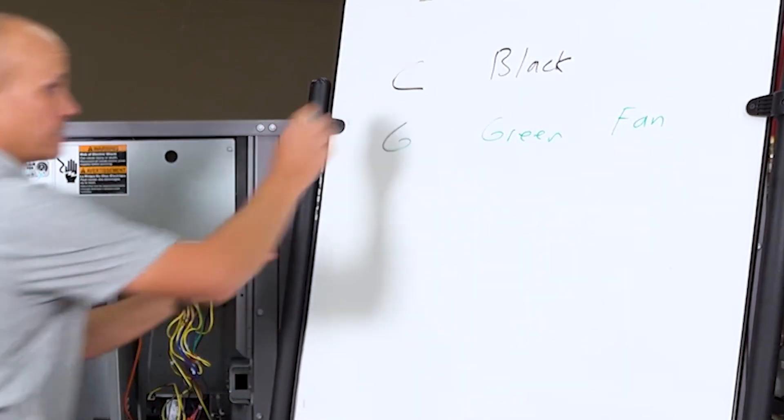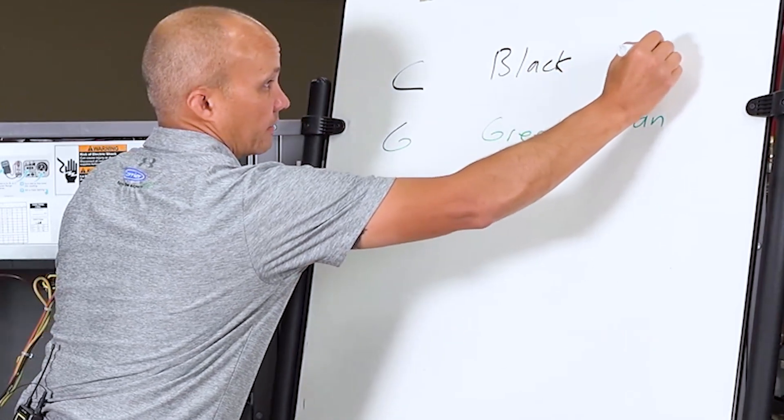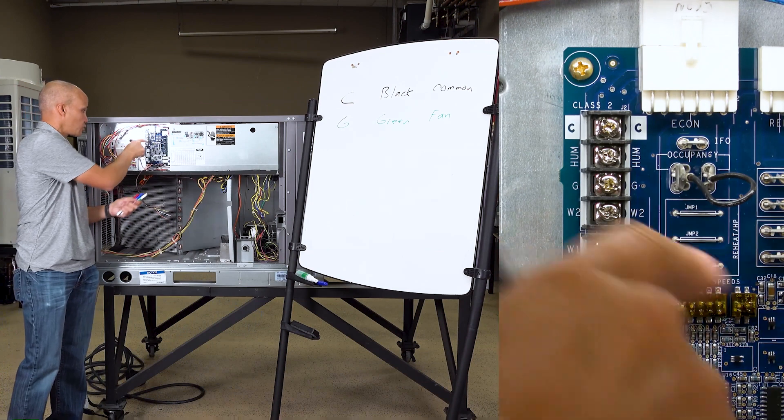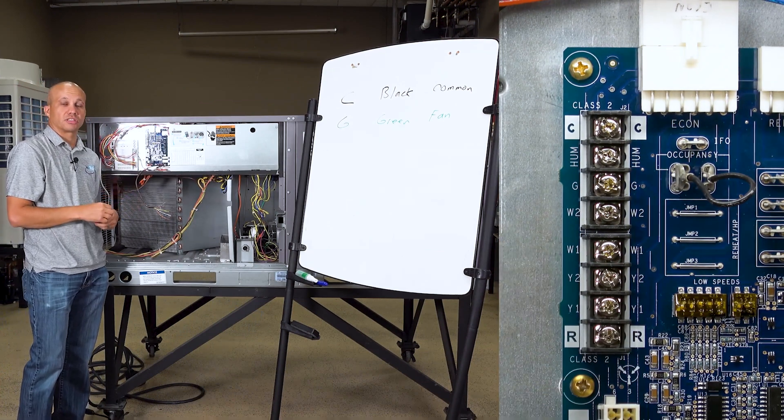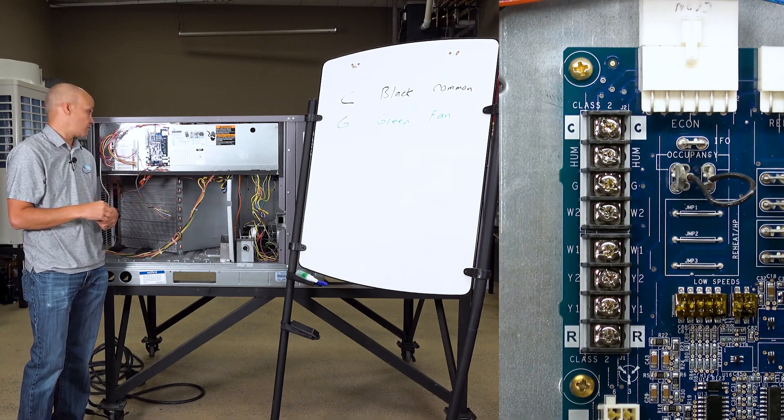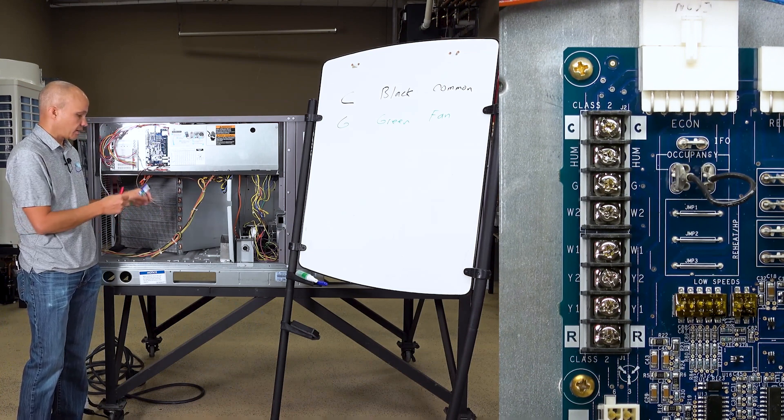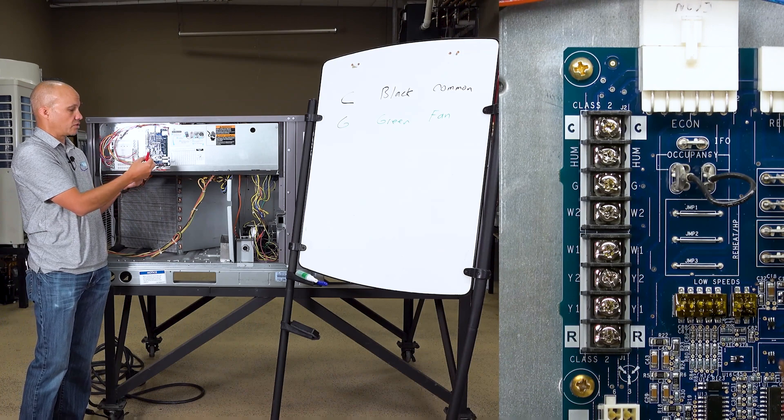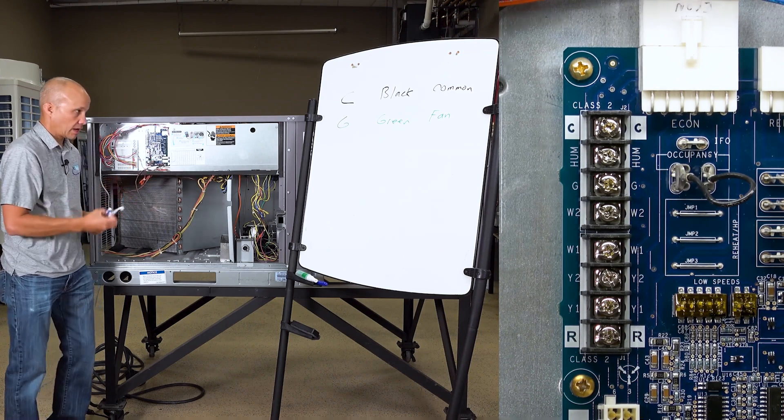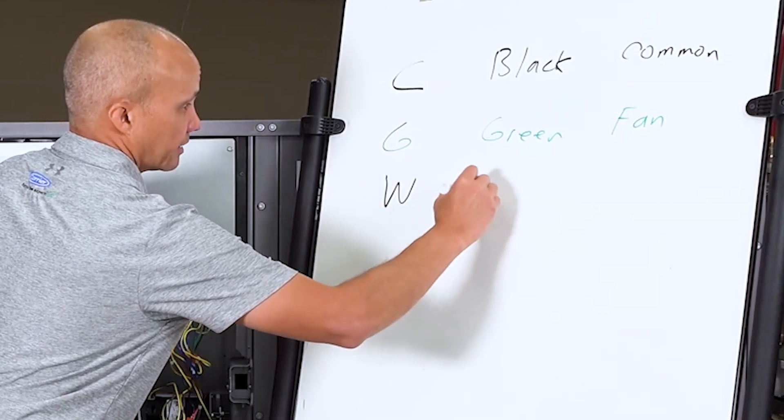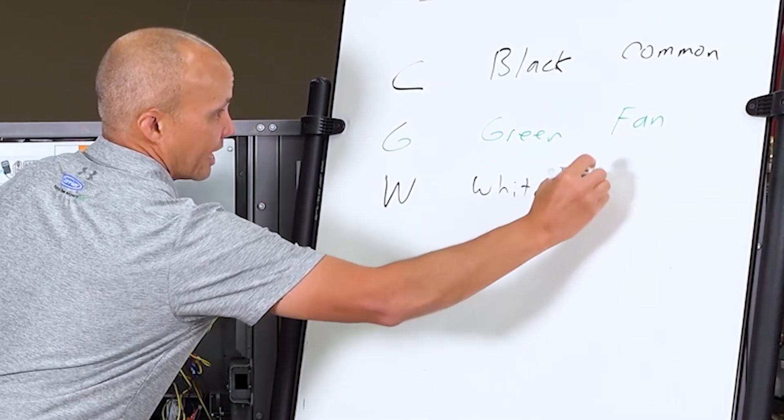The next one on here is W2, which we're not using in this case. W2 would be second stage of heat. Below that is W1. We are going to use W1. In our case for W1 we're going to use it with the white wire. I can't really do that on the board here with a whiteboard, so we'll just do it in black. That'll be white and that'll be my heat.